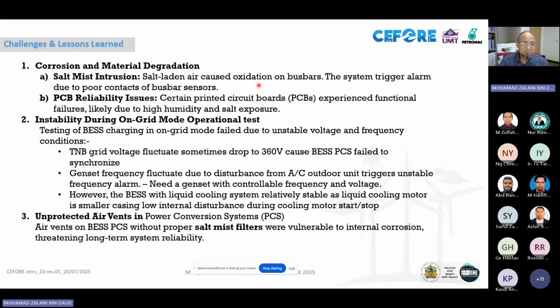And then secondly, when the battery energy storage arrives, because it comes with 50% state of charge capacity, we need to charge it first. To charge it, we need to operate it in on-grid mode. Basically, we found that the TNB grid we use to charge the battery is not stable here. Sometimes the voltage drops to, for example, 360 volt, causing the battery energy storage PCS to fail to synchronize. So when the voltage drops or is unstable, we cannot operate in on-grid mode and we cannot charge our battery.